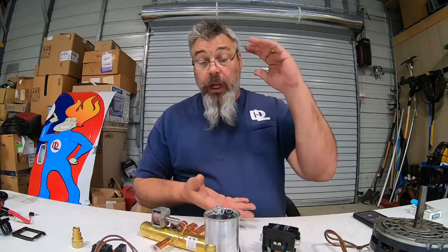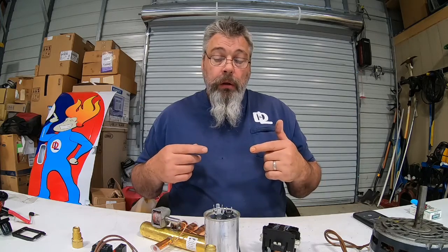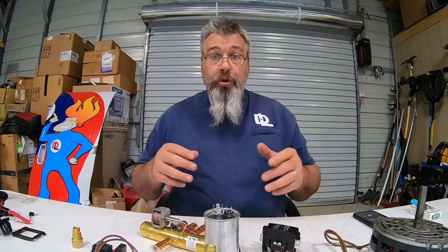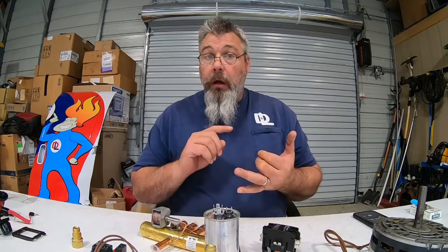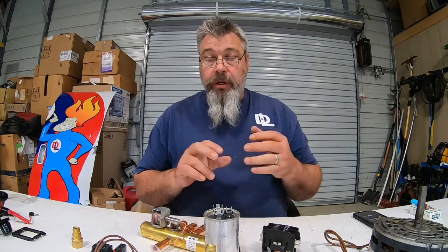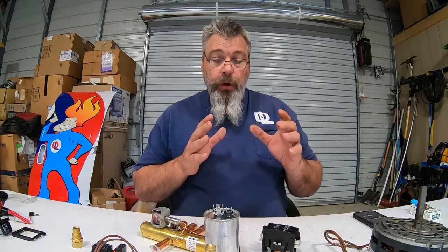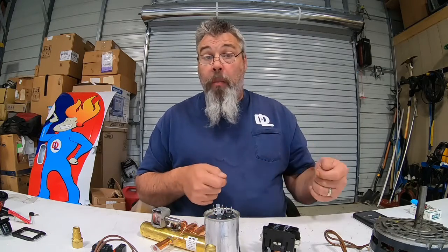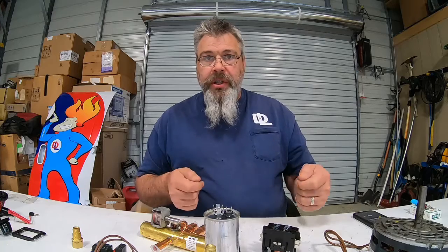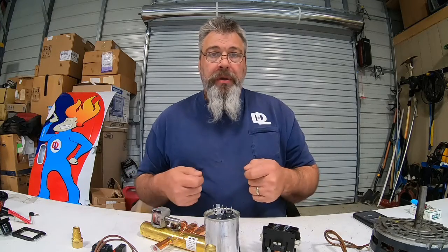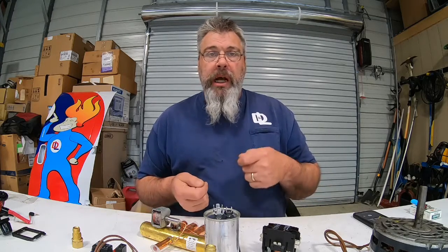So they look like a tin can in the middle of your unit outside. The best thing I can tell you on that is it's enclosed, it's hard to test. There's a special meter that you put on them called a megohmmeter. You can meg out a compressor, is what we refer to as megging it. We also can ohm it, ohms of resistance, or check it to ground. Compressors will short out in the summertime because they're running.